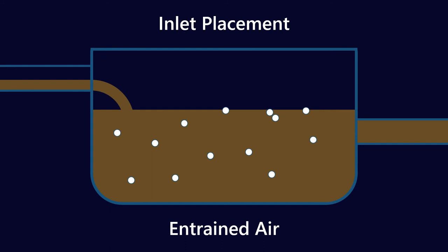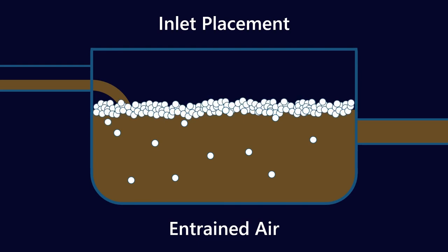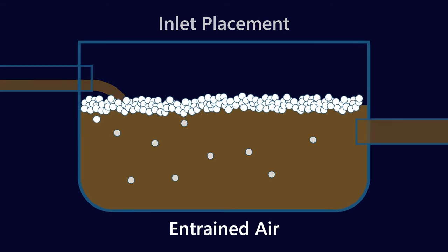Let's talk about the inlet placement as well. If the inlet is too high, what that's going to cause is, on the suction side, potentially foam or bubbles or just straight air to end up on the inlet. That's going to mean that you have a whole bunch of entrained air that ends up in your application. It's obviously pretty undesirable.